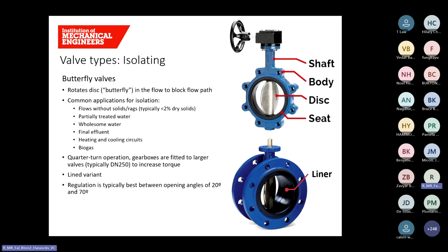I mentioned the valve is quick to operate, and that's because it's a quarter turn operation. Gearboxes are required on larger valves to help increase torque, and that allows for proper closure. Lined variants are also available. This is where a protective lining is bonded to the butterfly disc and internals of the valve body. The material is typically EPDM within the water industry. It's worth covering that this valve can also be used for flow regulation duty. It typically provides best flow control between about 20 and 70 degrees open.